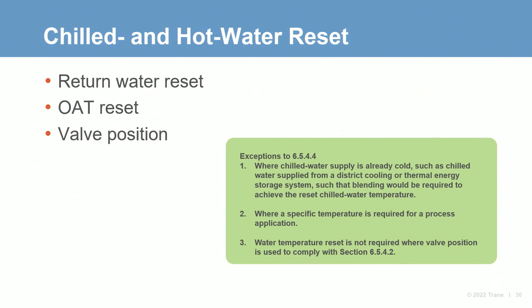Chilled and hot water reset are addressed, which requires automatic resetting of the fluid temperature set points once the system gets larger than 25 tons. Three common ways to accomplish this could be return water reset, outdoor temperature reset, and valve position. There are a few exceptions for district energy and process applications where applicable.